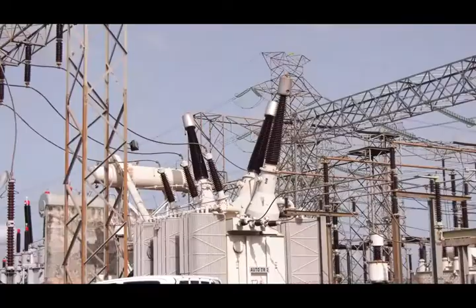What is being awaited now is a fire protection system in the transformers. So what we've done here is add 2 new transformers of 60 MVA each. That means an additional 120 MVA to the existing 60 MVA, which is 180 MVA, and it increases the total power intake in addition by 70 megawatts, which takes you to about 190-something megawatts for this DISCO.